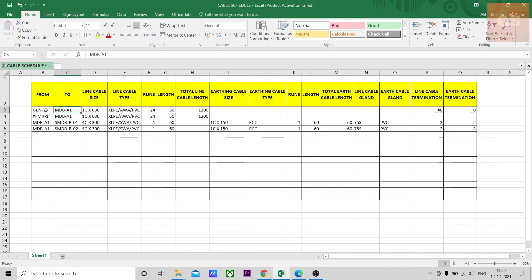It is your duty to find out the shortest distance, find the position or the location of these two incoming and outgoing equipments and then find the shortest route between them through a cable tray. Sometimes the cable will be going through the cable tray or it might be going through a cable trench. Find that out and then calculate the shortest length. The runs and length multiplying it will give you the total length.